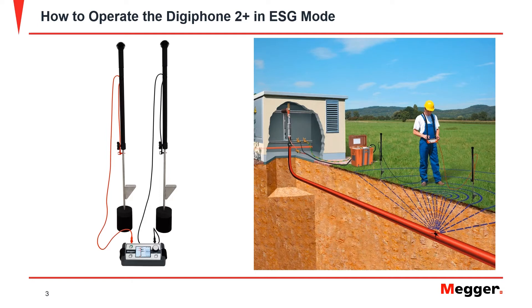In order to locate a sheath fault and buried cable, a DC pulse generator is connected to the faulted cable and sends a DC pulse to the fault. The pulse dissipates through the ground surrounding the faulted area of the cable. The two measuring probes from the ESG are used to measure the step voltage and indicate the direction that the fault is in.